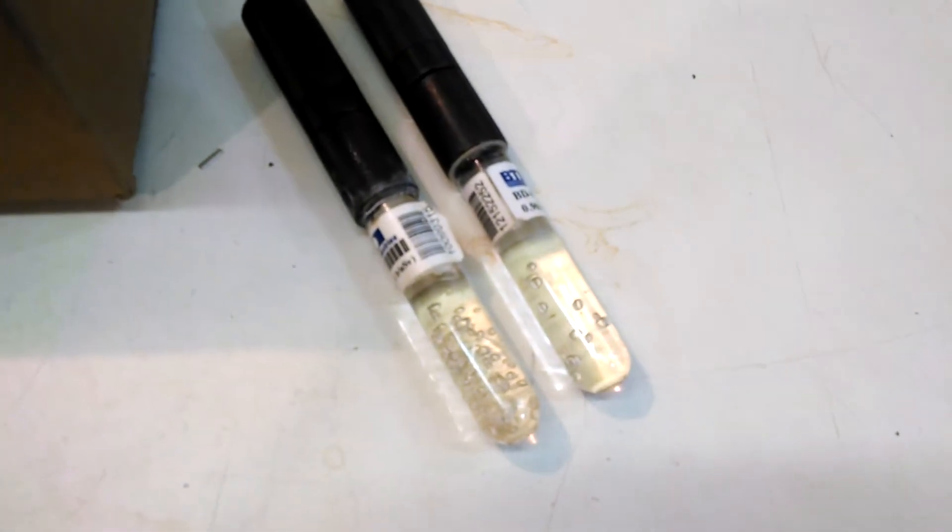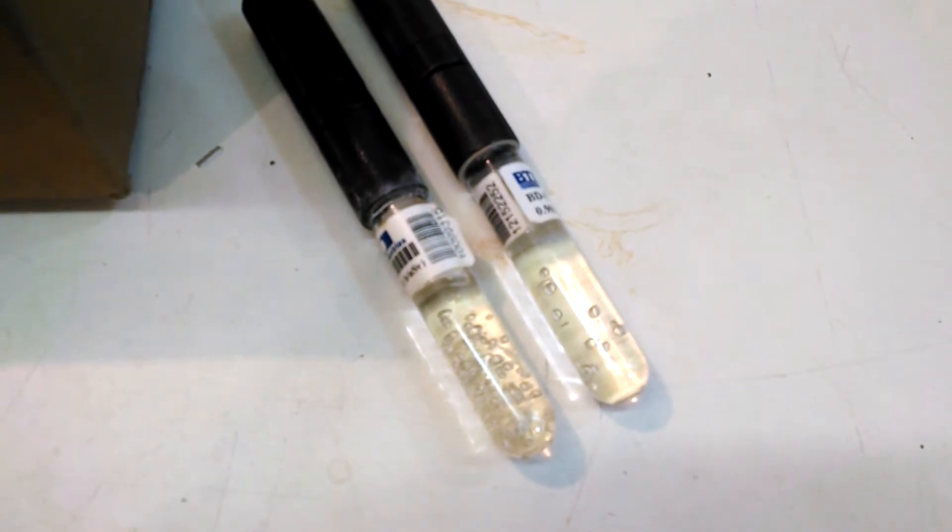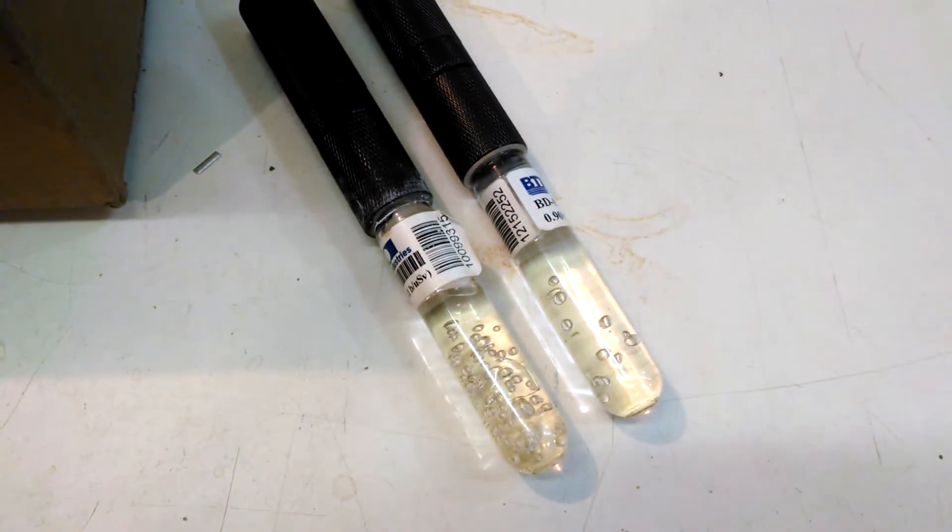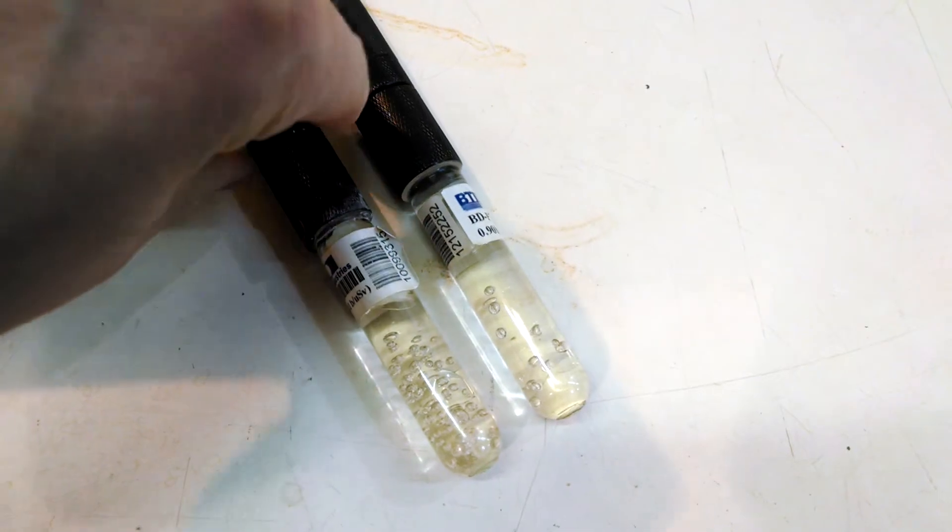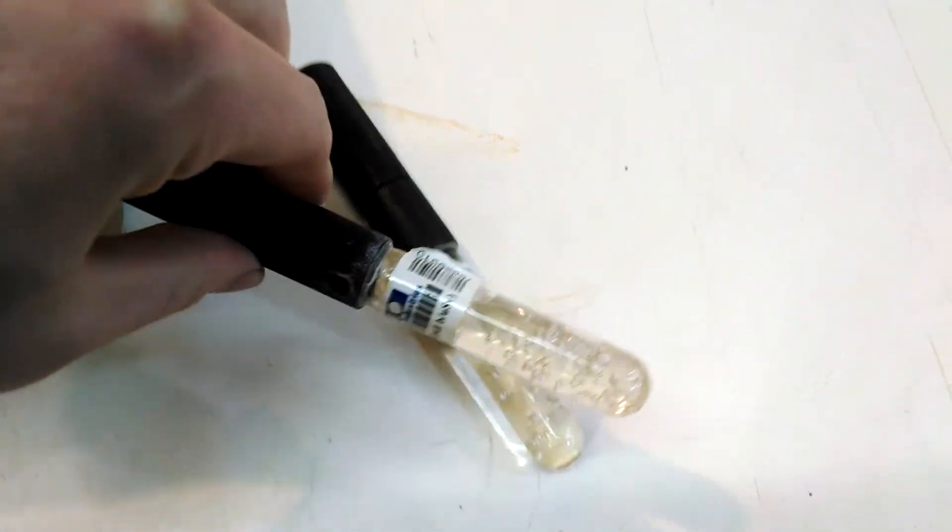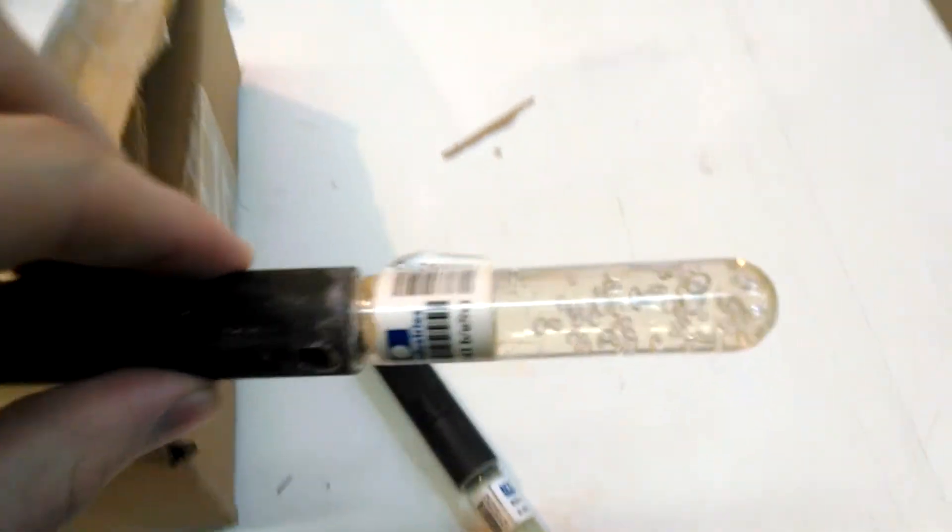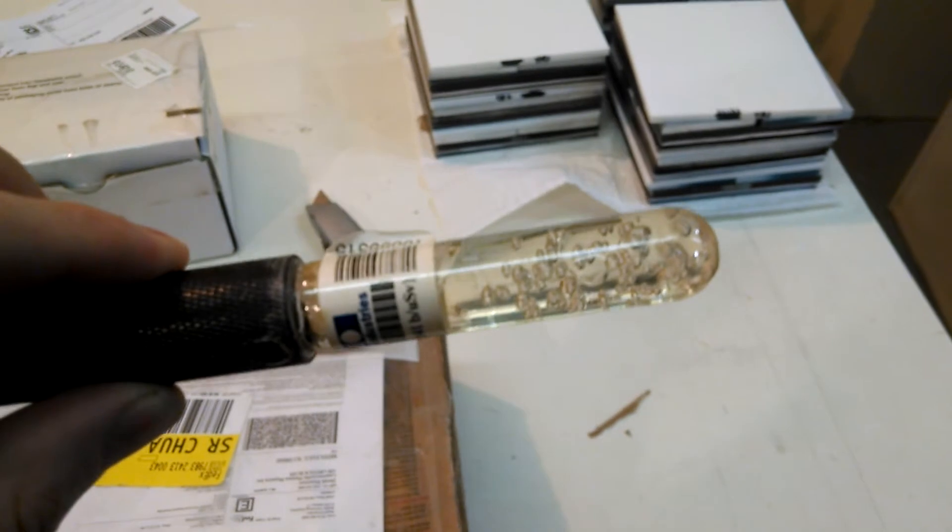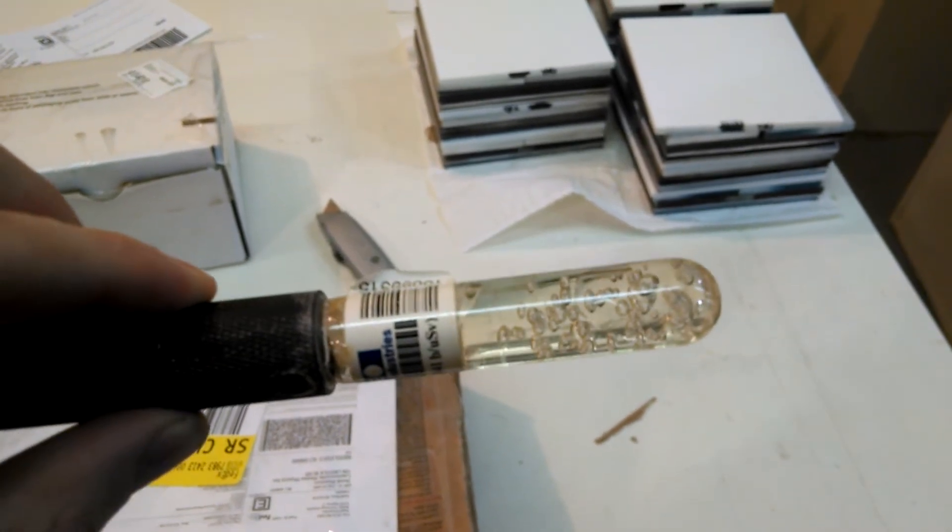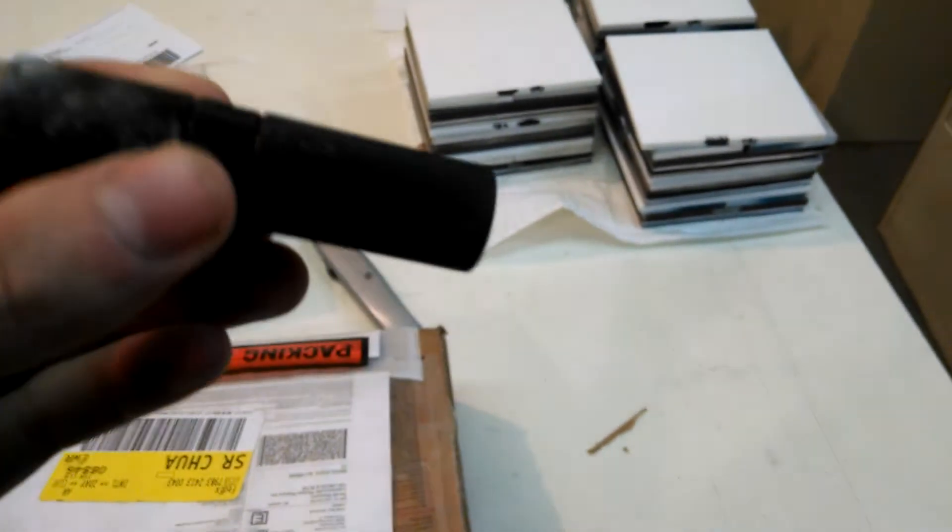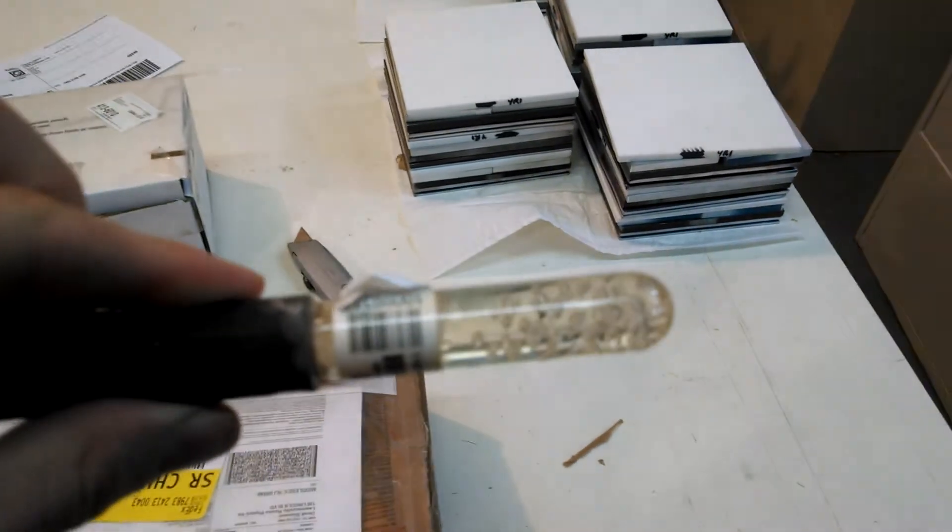Well, the bubble detectors have a superheated fluid in them, and when that fluid is hit by a neutron during an experiment, then a bubble will form. But they're supposed to go away when you reset them, so these aren't resetting anymore.